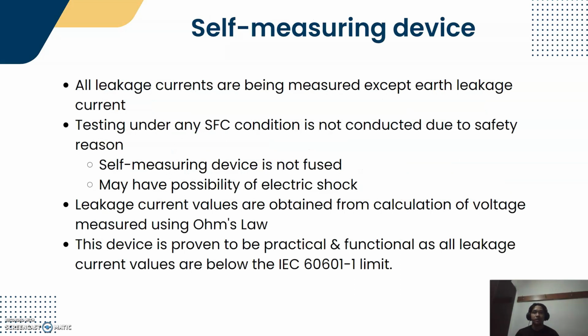For the self-measuring device, all four leakage currents are being measured except earth leakage current. Testing under any single fault condition is not conducted for safety reasons, as our self-measuring device is not fuse protected and we may have the possibility of having an electric shock. Leakage current values are obtained from calculation of the voltage measured by applying Ohm's law.